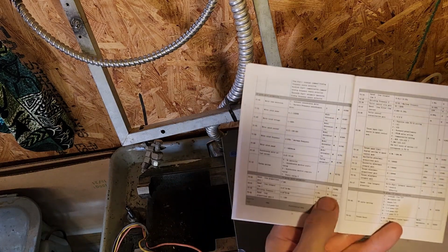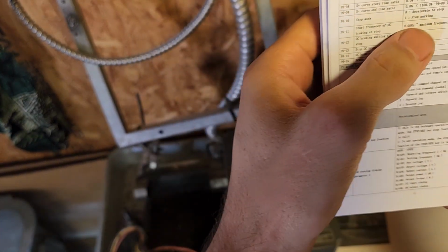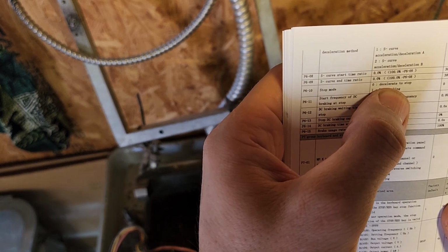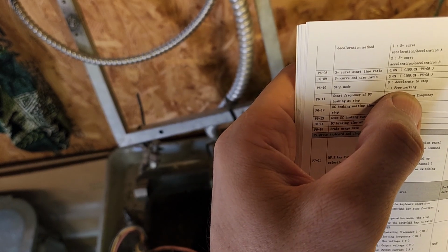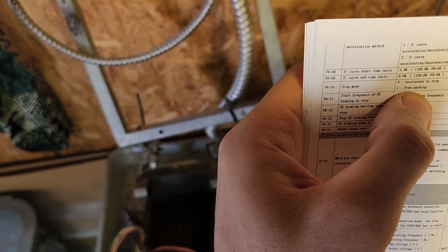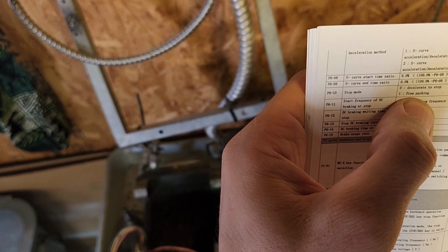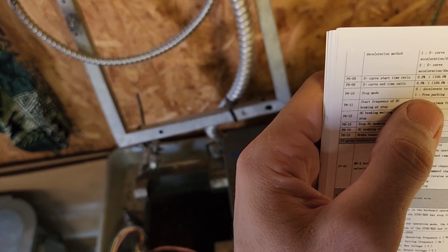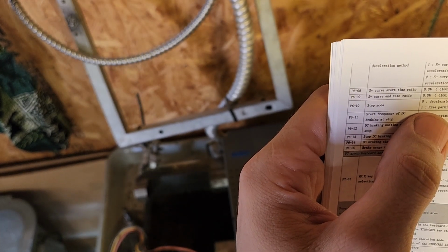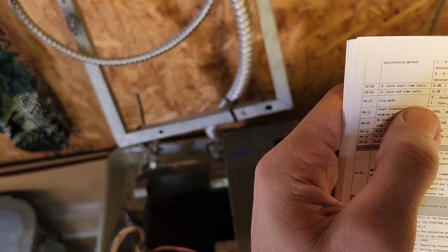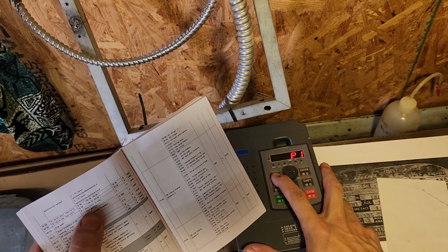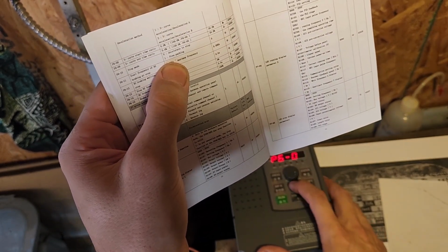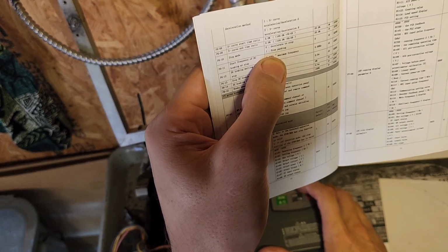So I'm going to look through the rest of these real quick and see if there's anything else I need to change. Looking through this, from previous experience, stop mode, decelerate to stop, means the VFD is going to try to slow down the motor and stop it. Free parking, I believe, is let the motor just cut the power and let it decelerate on its own. I would much rather use that, because based on other motors I've done, I've had it fault out because it's trying too hard to stop the motor. So I'm just going to change this to 1. That's P610. I'm going to change it to 1.